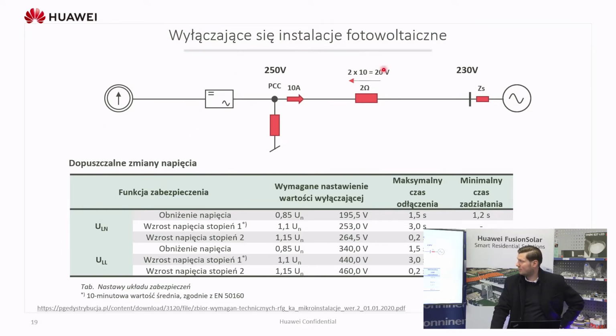The reason for this is quite simple. Here's a simplified schematic of our PV plant connected to the local grid: we have the transformer station, our current source which are the PV modules, and our inverter. Usually the problem is that the inverter wants to be a source in this layout, so if it wants to pump power to the grid, a voltage difference might be created. Our reference point is 230 volts, but if the inverter wants to be a source, it must slightly raise the voltage by a few volts usually. How much it raises the voltage also depends on the line impedance.